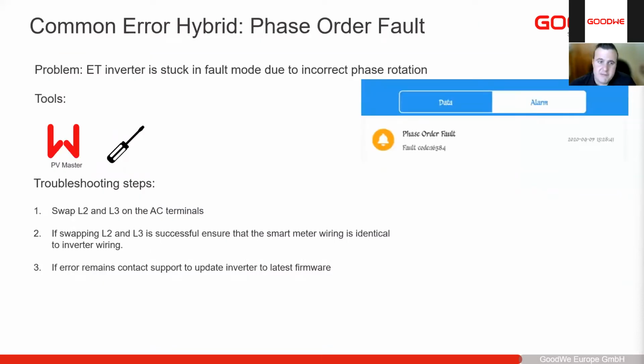Next on our three-phase devices is phase order fault. Always when you install a new ET, you connect the grid and everything up to the device, and then it's stuck in fault mode. In the alarms, you can see phase order fault. That just normally means that our phases aren't in the correct rotation on the device. Normally you just swap L2 and L3 on the AC terminals under the inverter or on your main breaker, and then that will resolve the phase order fault. So switch everything off, switch the cables around, switch it back on again, and that fault should be cleared.